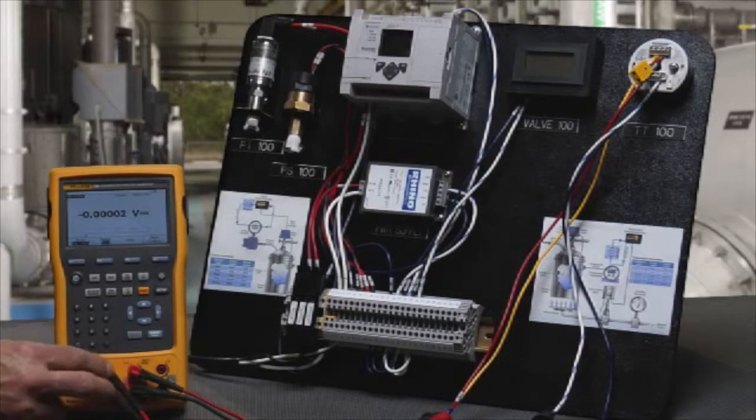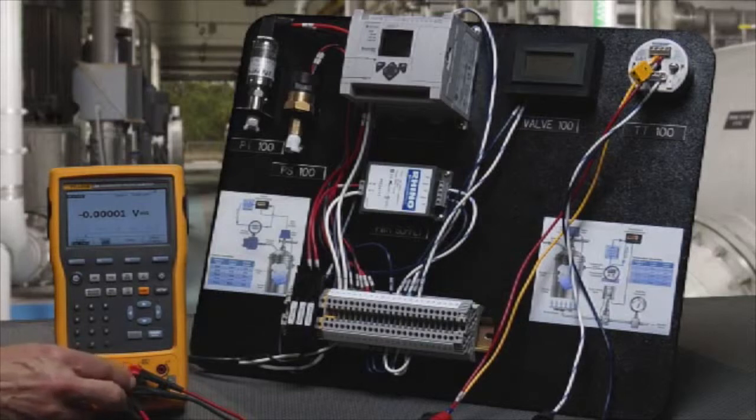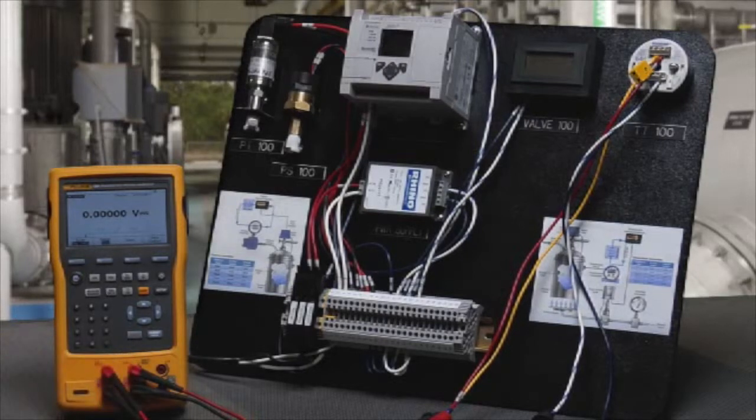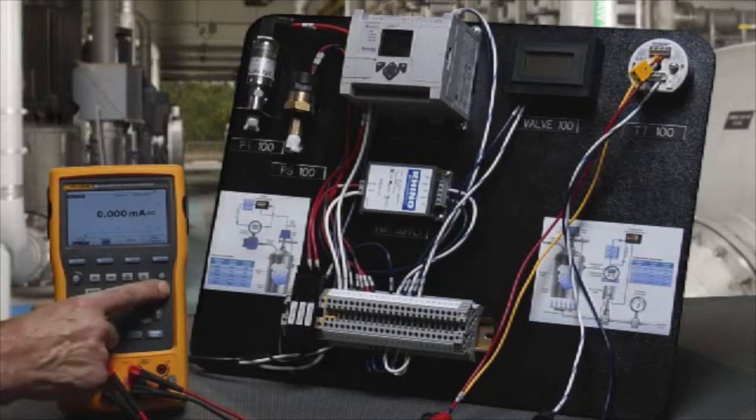We're going to simulate an RTD input into the transmitter while simultaneously measuring the milliamp output signal. To initiate the test, select measure milliamps and turn on loop power.